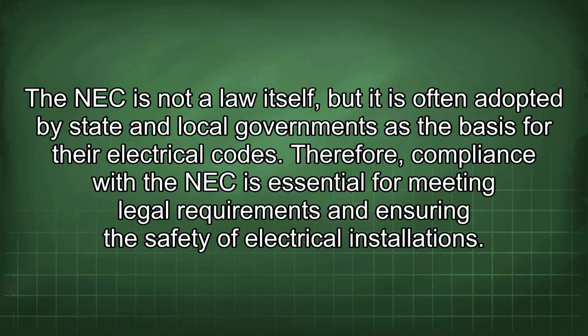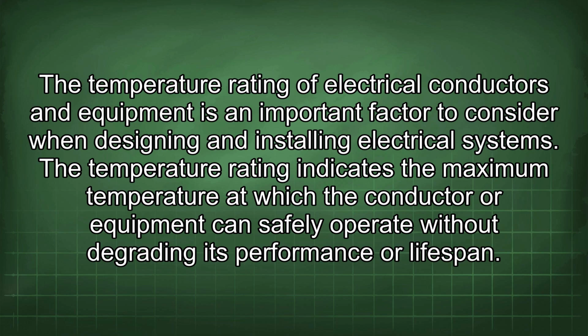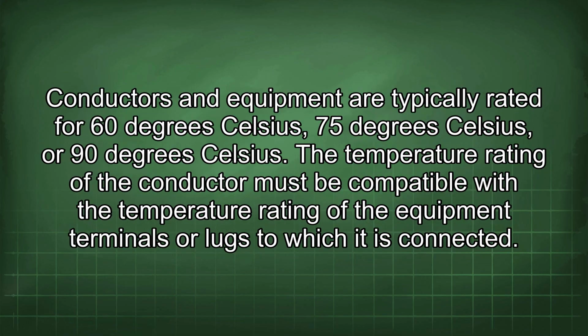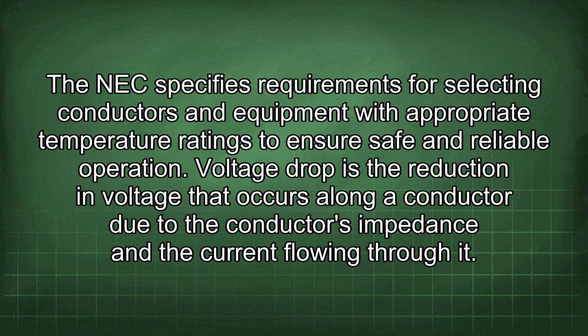electrical installations. The temperature rating of electrical conductors and equipment is an important factor to consider when designing and installing electrical systems. The temperature rating indicates the maximum temperature at which the conductor or equipment can safely operate without degrading its performance or lifespan. Conductors and equipment are typically rated for 60 degrees Celsius, 75 degrees Celsius, or 90 degrees Celsius. The temperature rating of the conductor must be compatible with the temperature rating of the equipment terminals or lugs to which it is connected. The NEC specifies requirements for selecting conductors and equipment with appropriate temperature ratings to ensure safe and reliable operation.